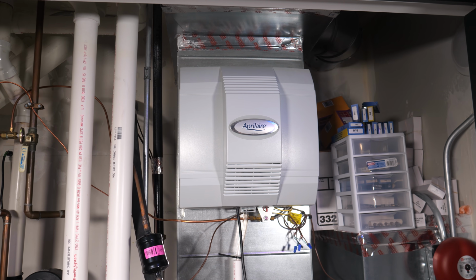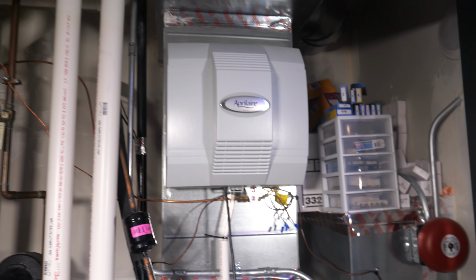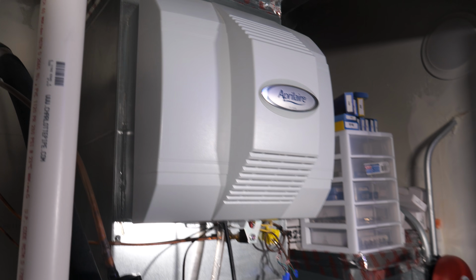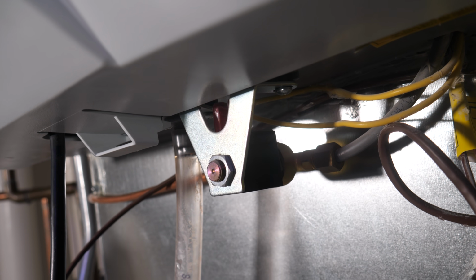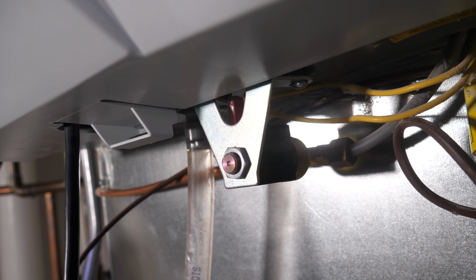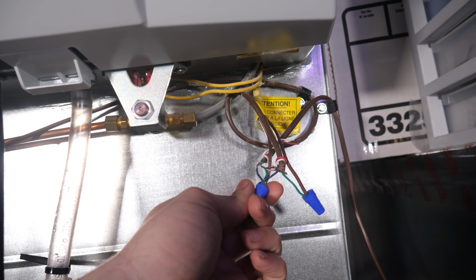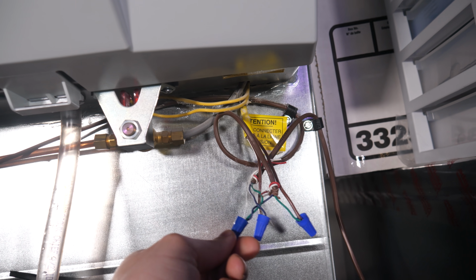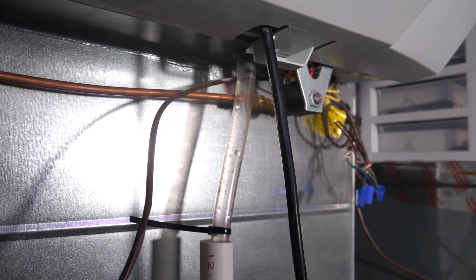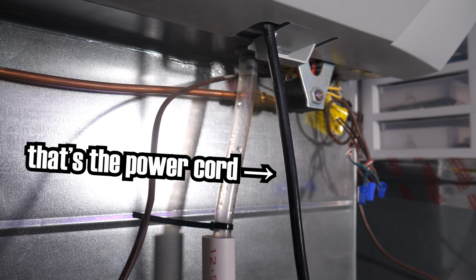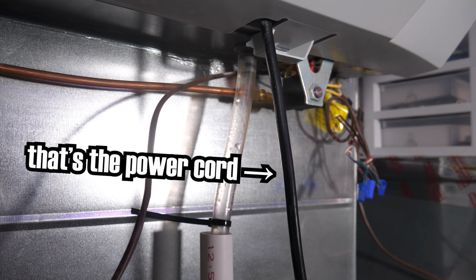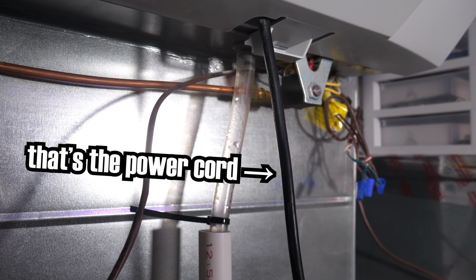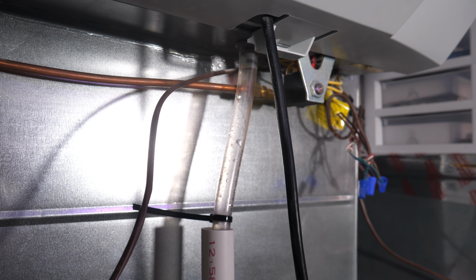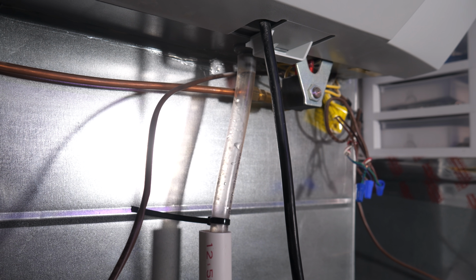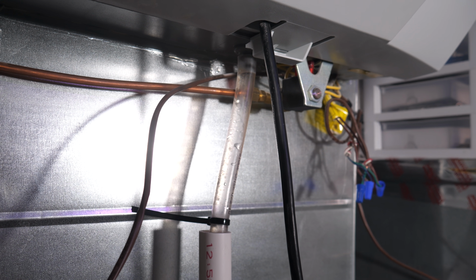Only power this thing up if the furnace is running and blowing air through the ducts. That water valve is powered by 24 volts AC, the same power that your furnace or air handler produces to send through your thermostat wiring for control signaling. The humidifier is also plugged into 120-volt line voltage for its fan motor, but the fan is controlled via a current-sensing relay which detects that the water valve is open. So if the water valve is open, the fan will run.